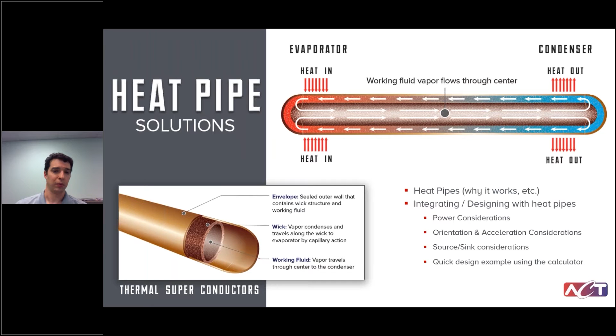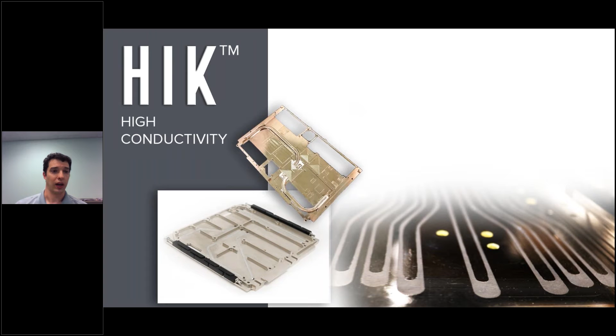We also want to think about the evaporator and condenser sizes. We want to maximize those to improve the overall assembly delta T. We'll do an example of this in a couple slides. Next up is a high K or high conductivity plate. High K plates are basically aluminum plates with heat pipes integrated into them to increase the conductivity from the basic aluminum, 167 watts per meter Kelvin for 6061. These can go up somewhere between 500 to 1,000 watts per meter Kelvin, depending upon the geometry. Because most of the frame is still made of aluminum, it has the similar weight and similar strength to aluminum. And we can normally route our heat pipes around critical features so that all of your bosses and mounting holes can be maintained.